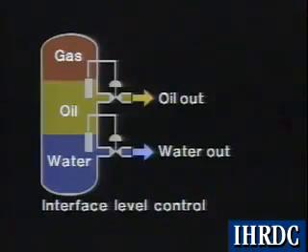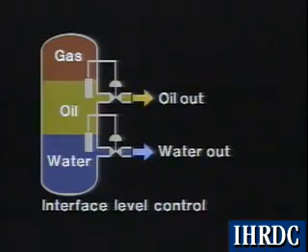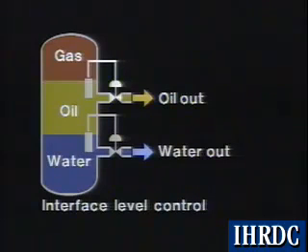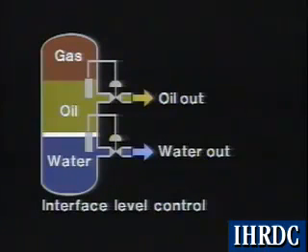Three different methods of control are often used on vertical three-phase separators. The first is strictly level control. A regular displacer float is used to control the gas-oil interface and regulate a control valve dumping oil from the oil section. An interface float is used to control the oil-water interface and regulate the water outlet control valve.